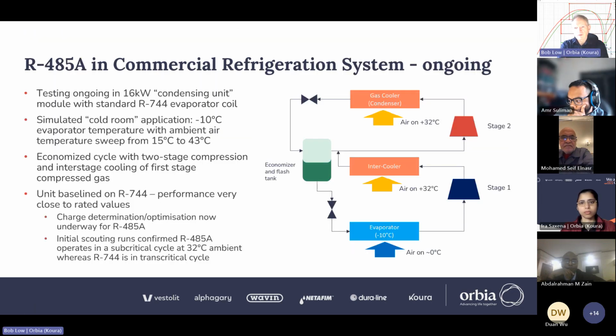Then moving on, we're running some more testing right now in our commercial refrigeration systems. This is a larger unit, a condensing unit. It's 16 kilowatts nominal capacity at minus 10 C. So it's a sort of large system with maybe 8 to 9 kilograms charge that you might use to keep a cold room cold or a walk-in freezer cold.